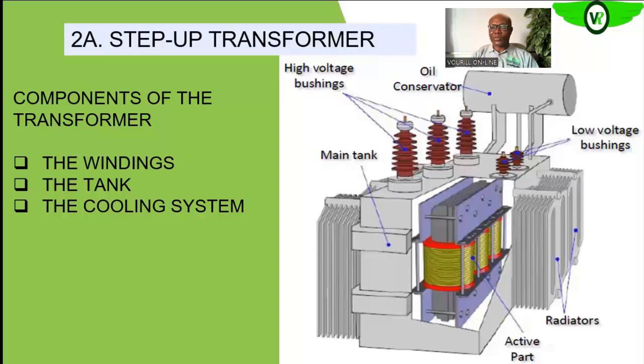So you see that with this kind of arrangement, the heat is taken from the windings through conduction by the oil molecules, and the oil molecules move away to either the tank body or to the cooling fins and give off that heat to the fin material, the metal used to make the fin. Then that heat conducted from the oil molecules into the fin is given off to the surrounding air molecules, and then the air molecules will help to take the heat away. So that is how the cooling is done in the transformer.